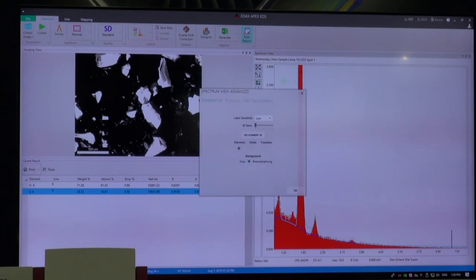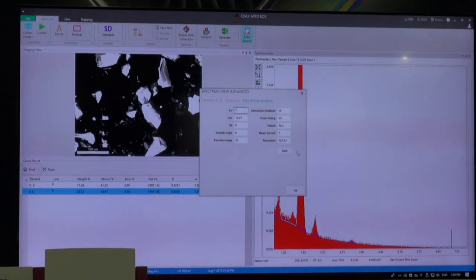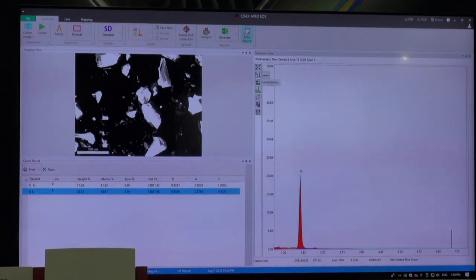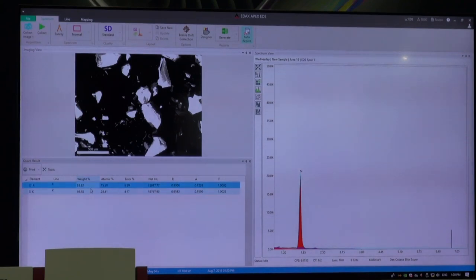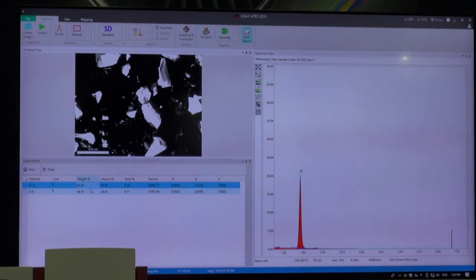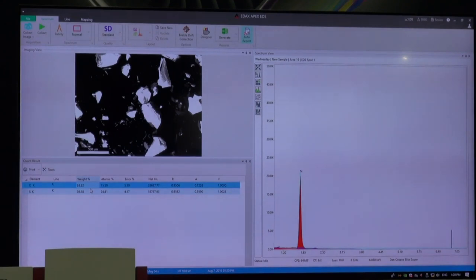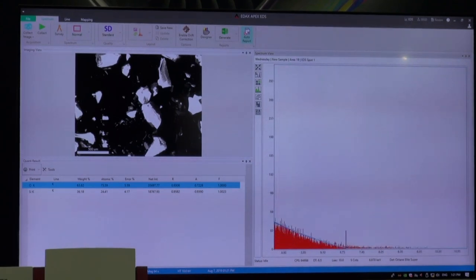If we start playing around with the actual landing energy — we guessed about 7 — it looks like it's a little lower than 7, but now I'm getting 63/36, which is much, much closer to silicon dioxide. That's just by changing by about 3 kilovolts, which is quite a significant charge buildup. If we get the wrong input parameters to our equation, the results are going to be wrong — same thing with the sample tilt. If we tell the software the sample is flat and it's not, we get deviations, and having the Bremsstrahlung model helps you see what those deviations are.